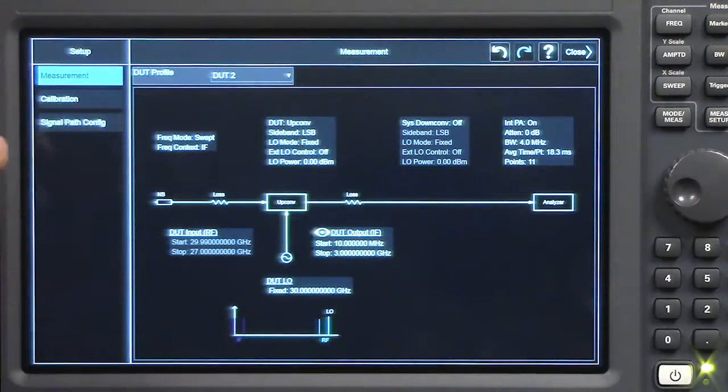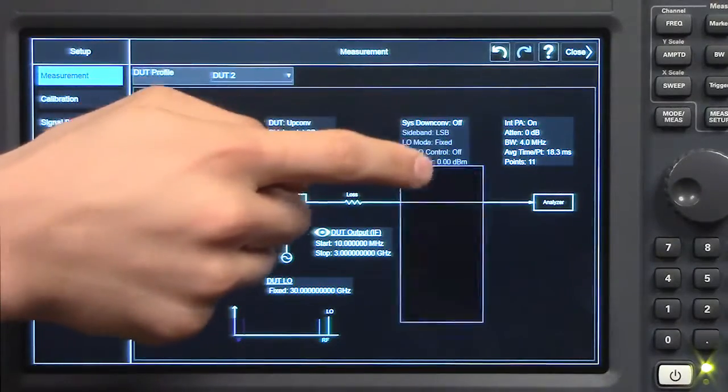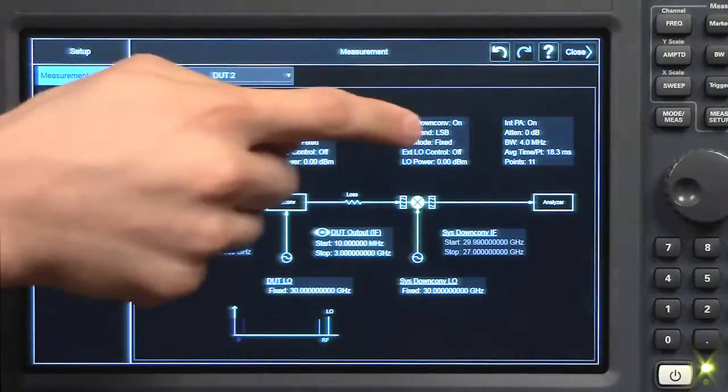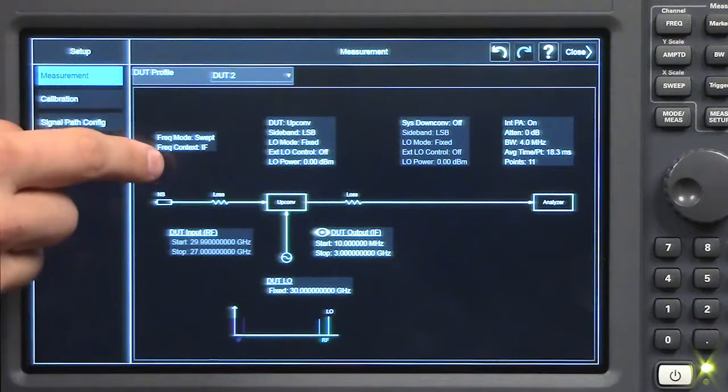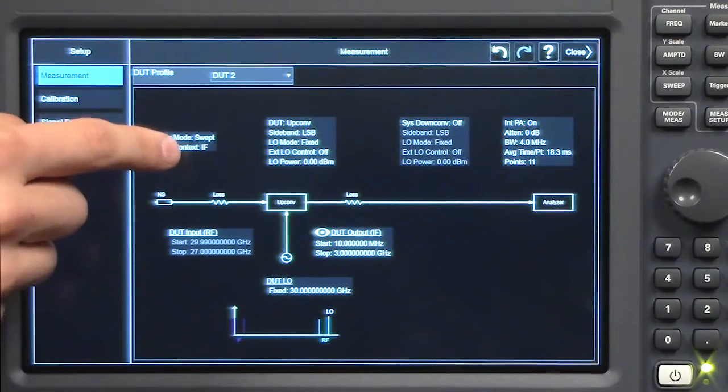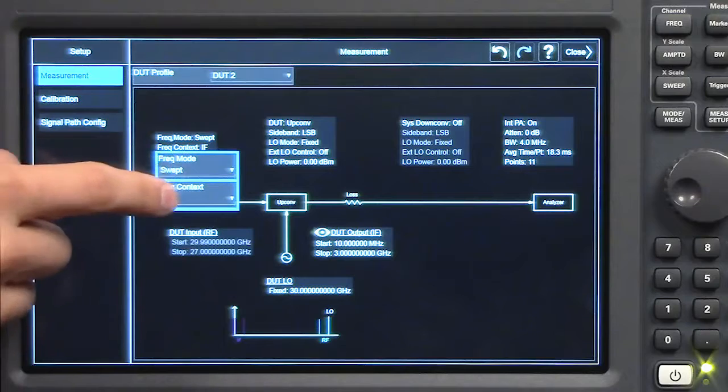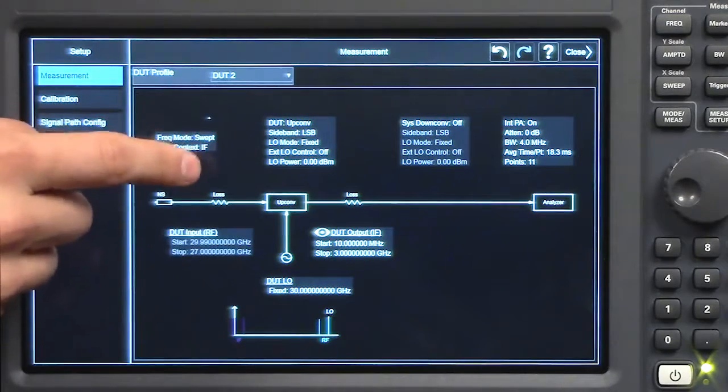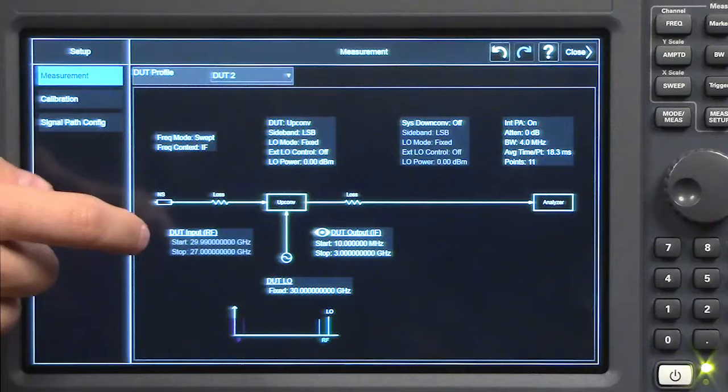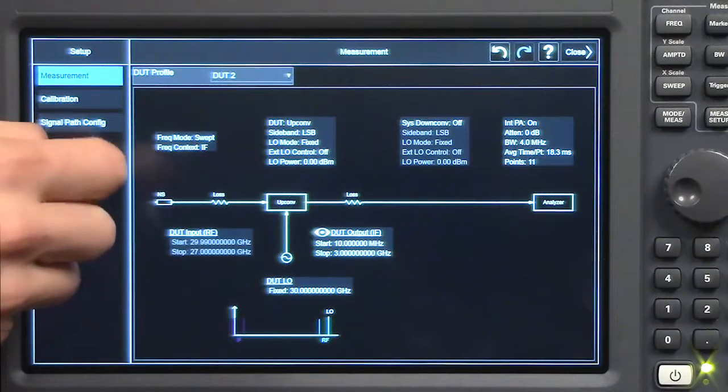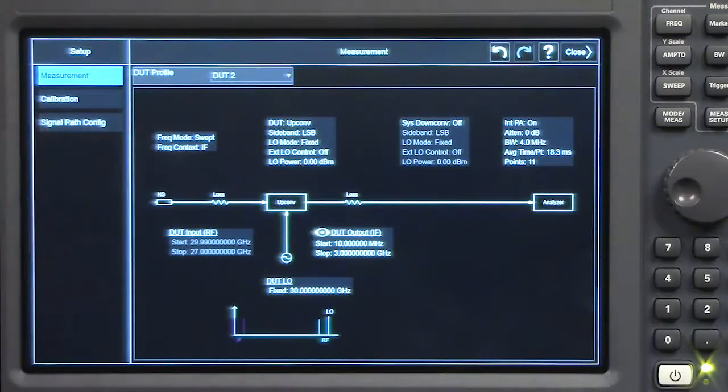We can also activate a system down converter if we wanted to. It'll include it in the calibration chain, but let's take that off for now. Here you can see the frequency context is set to IF. We also have a choice of RF. That determines the different units that will appear on our measurement window, whether our measurement is with respect to the IF or the RF frequencies.